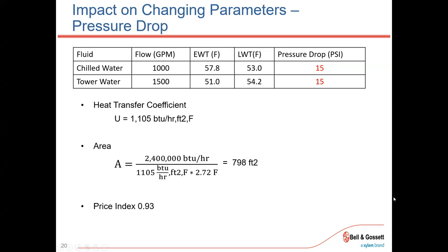So you can increase your pressure drop, increase your velocity, increase your turbulence, decrease your surface area, resulting in a lower price. But then again, if you have that pressure drop all the time, if you could avoid it, let's say it's not a zone that's being balanced back as if it would be wasted anyways. If it's a zone that you're basing your design system pressure drop across, it likely would not be necessary because over the life of the product, it would consume more power than you'd be saving for the 7% reduction.